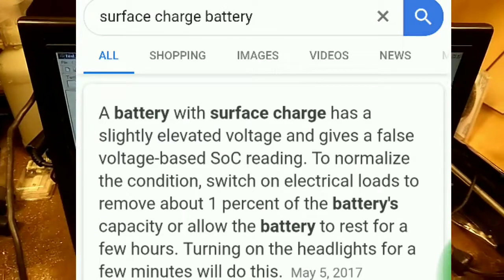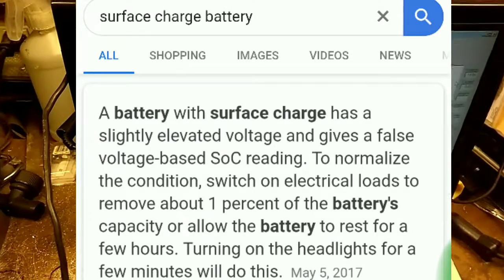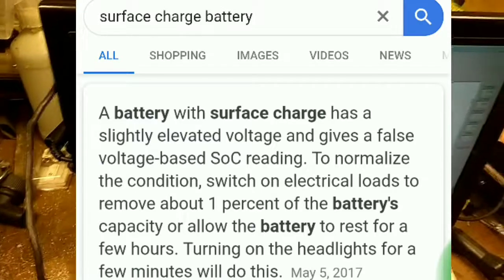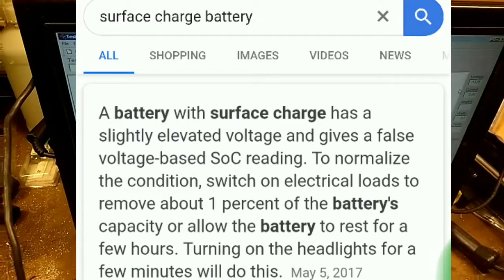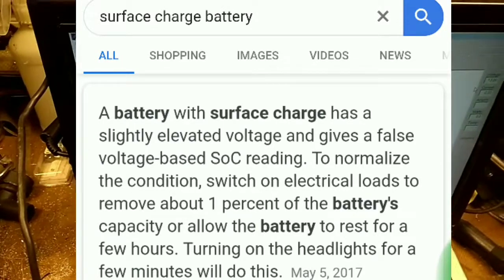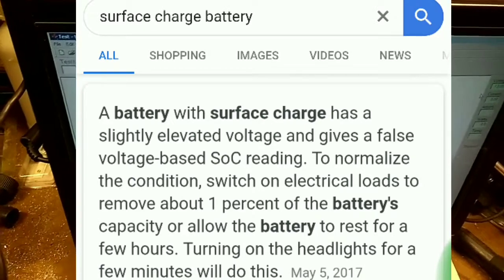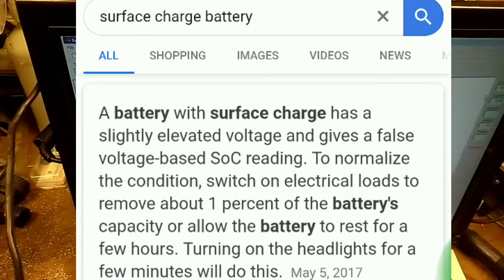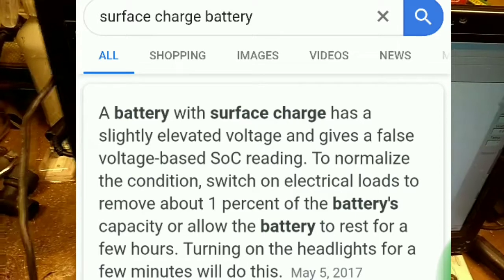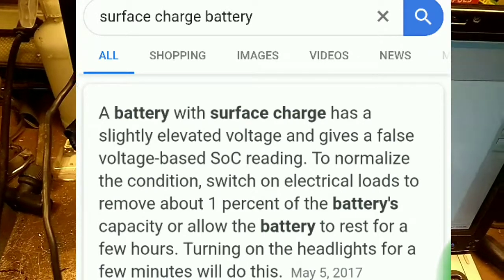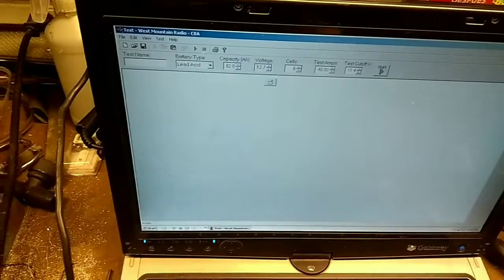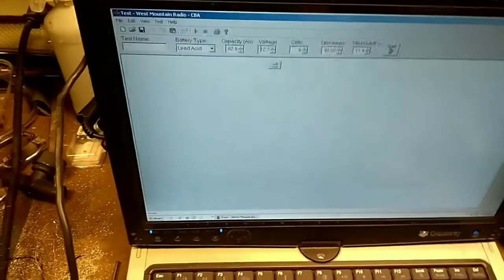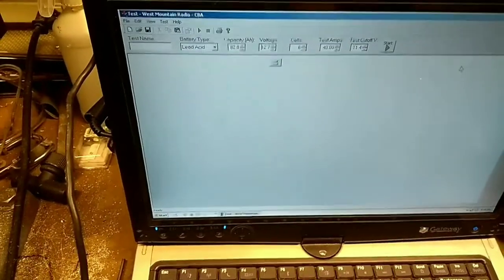Now, in a couple of my email chains back and forth to other people I've discussed this phenomenon called surface charge, and that is what we are experiencing right now. It is basically an overcharge, an over voltage condition that occurs on the surface of the plates. So in order to get rid of that we can either leave the battery sit or we can do a 1% discharge.